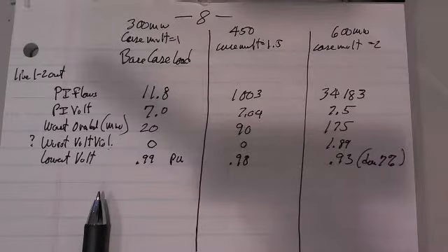Well, he says, this is a very hot day, and it was the middle of the afternoon, and we're watching the contingency voltage at a certain point, not too far out of the Minneapolis area. And it's just dropping, and maybe it was like 5 or 6%. It was just on the edge of disaster.